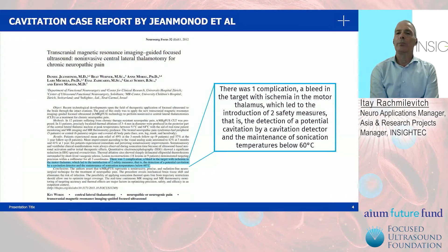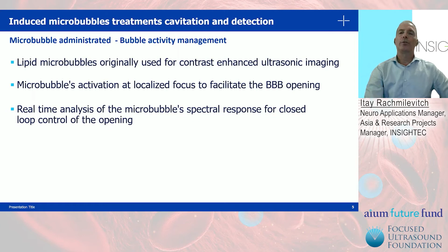The difference is, of course, that cavitation in the ablation treatments is induced by pressure, not by administered bubbles, whereas in BBB treatments, we are actually injecting the microbubbles in order to activate them at a very localized location to facilitate the BBB opening. The real-time analysis of the microbubble spectral response is being used for closed-loop control. We call it a controller of the opening and the required spectral dose.